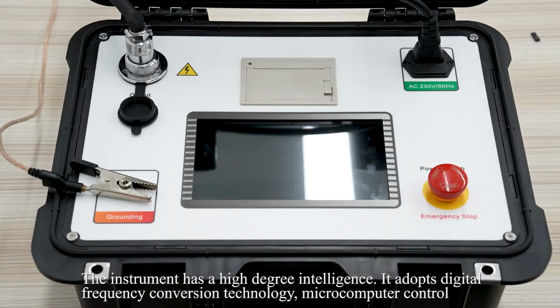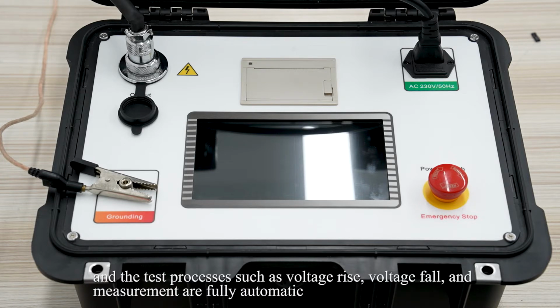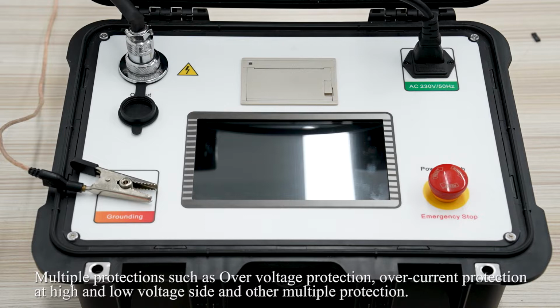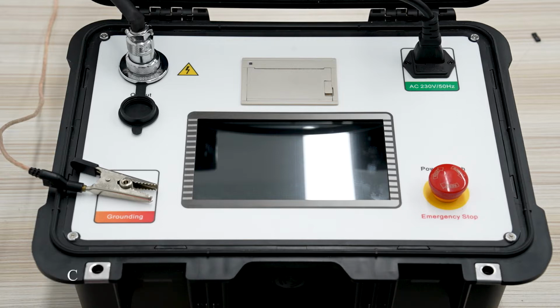The instrument has a high degree of intelligence. It adopts digital frequency conversion technology and microcomputer control, and the test process, such as voltage rise, voltage fall, and measurements, is fully automatic. It has multiple protections, such as overvoltage protection and overcurrent protection at the high and low voltage sides. High voltage current and voltage data are obtained directly through sampling at the high voltage side, so the data are true and accurate.